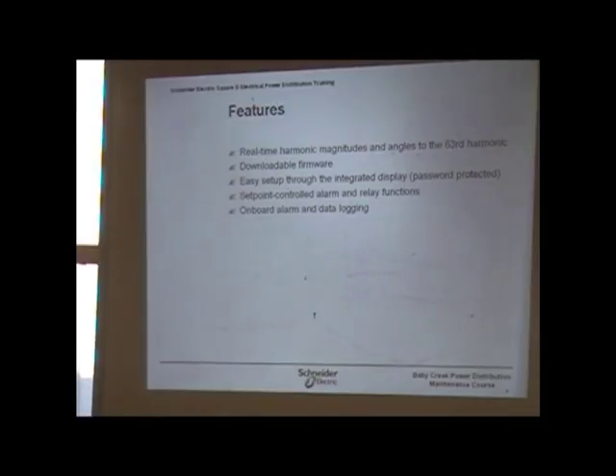monitoring purposes, meaning monitoring from a remote location. You could have those circuit monitors, including the power meter, or not the power meter, but the trip unit on the breaker out there on the low voltage switchgear. That could actually be displayed via the power logic program, or you can monitor it from a remote location, like your control room or a SCADA system, so you're able to see it.